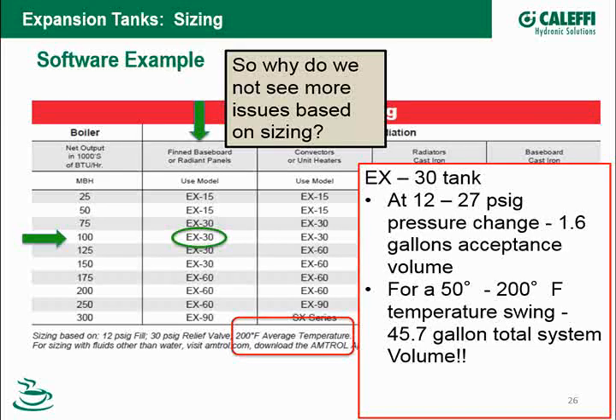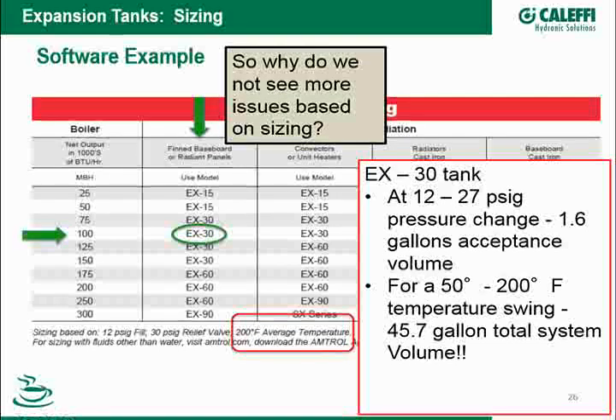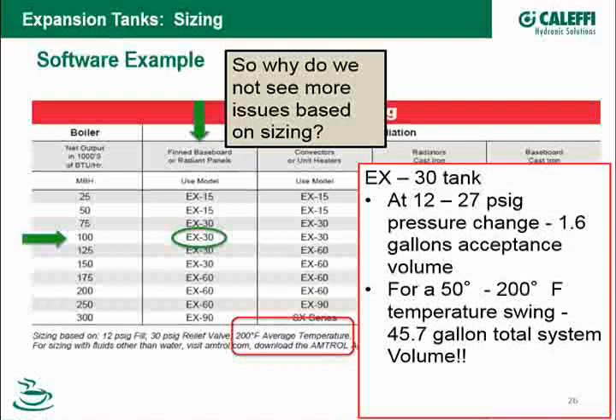So, questions about sizing? Yes, Jody, a question came in concerning sizing. When does the need for an ASME expansion tank come into play as it relates to sizing? Well, from the sizing process, the tanks, whether they're ASME or non-ASME, are sized properly. I'm going to go with the cop-out answer: ASME is required when an engineer specifies it.